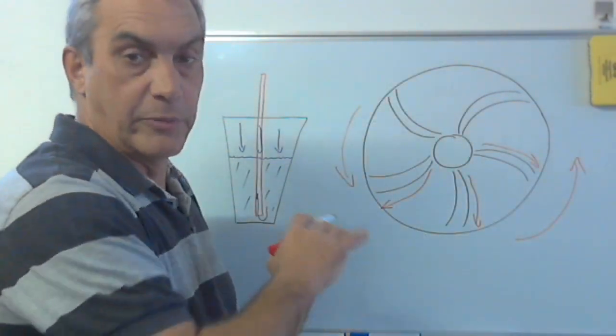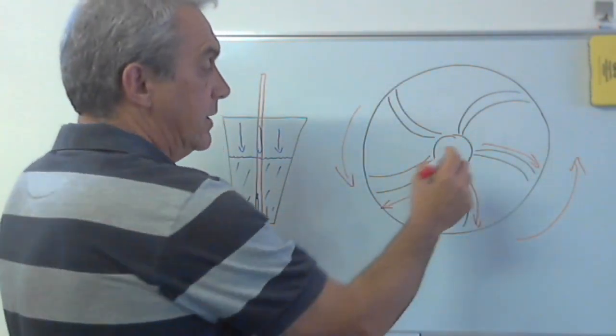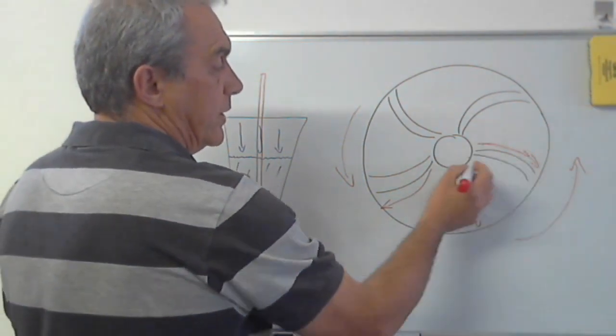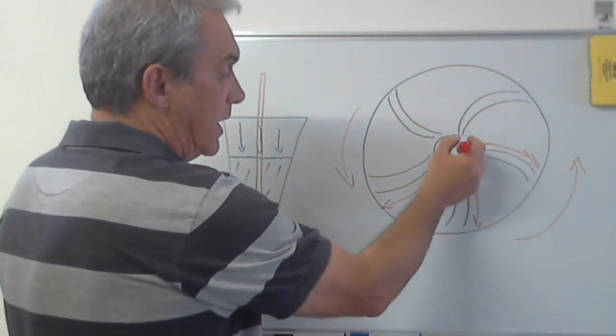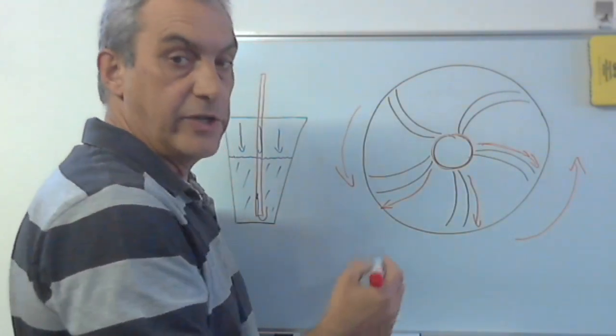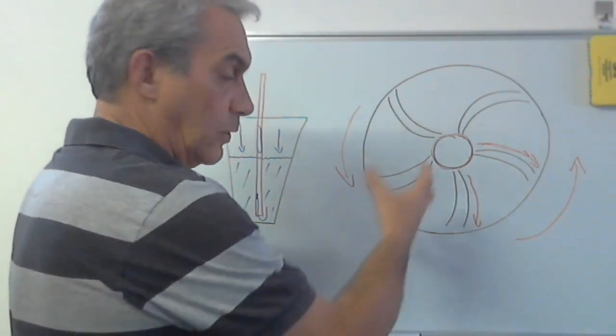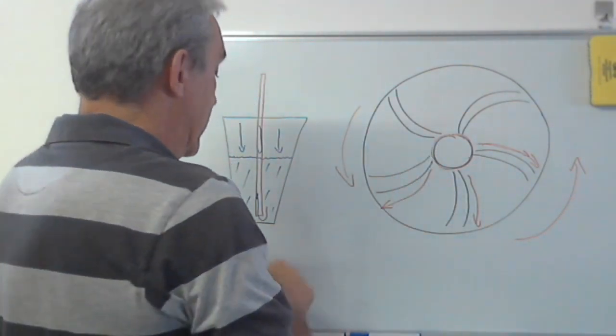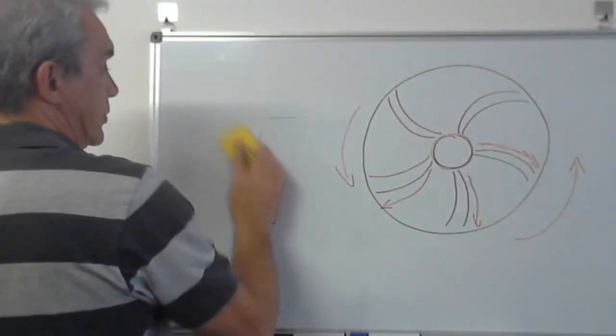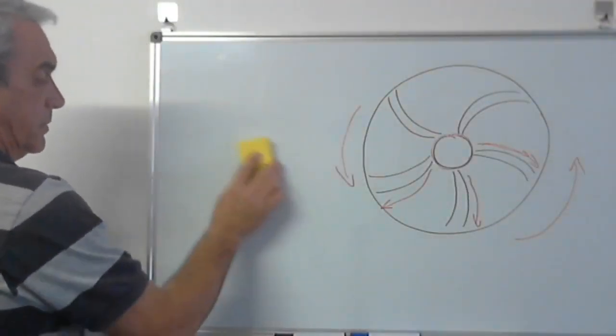But because this impeller was primed, completely filled with water and no air, the minute you move that water away, what are you doing behind it at the eye of the impeller? You're actually creating a vacuum, a low pressure zone. And if we draw a pump quickly, I'll show you in principle what's actually happening.